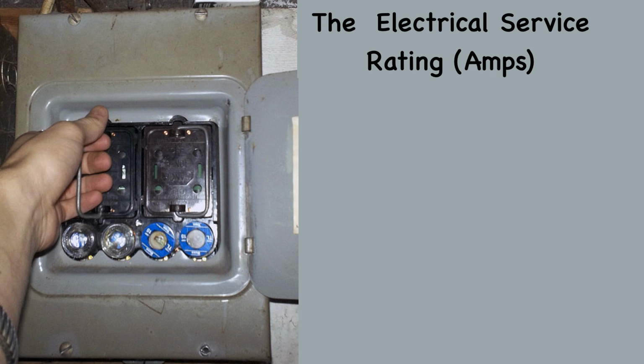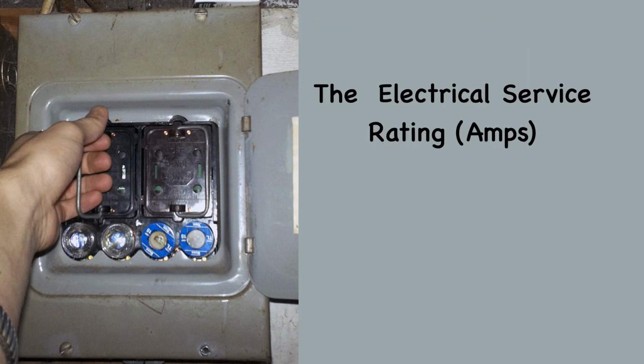Where an electrical service was installed before the early 1960s, and has not been updated, it may have a fuse panel, which protects individual circuits with screw-in or cartridge fuses. The use of fuse panels and circuit breaker panels for residential wiring follows this historical pattern. 30-amp fuse panel: installed before 1950, these service panels provide only 120 volts to circuits. Such a service provides insufficient power for modern usage, and generally needs to be updated. 60-amp fuse panel: installed from 1950 to about 1965, these provide 120 and 240 volts of power, but are still insufficient for most homes. An update is usually needed.